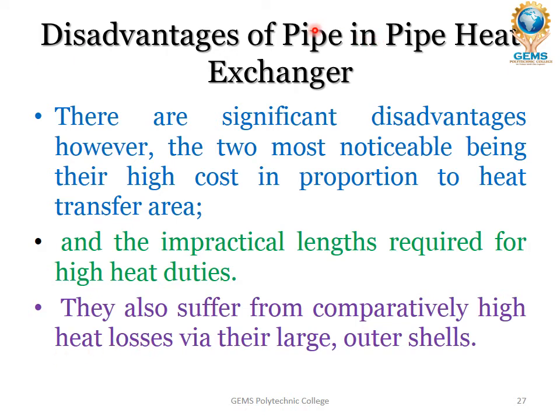Disadvantages of pipe in pipe heat exchanger. There are significant disadvantages. However, the two most noticeable being their high cost in proportion to heat transfer area and the impractical lengths required for high heat duties. They also suffer from comparatively high heat losses via their large outer shells. Through the large outer shells, high heat losses.